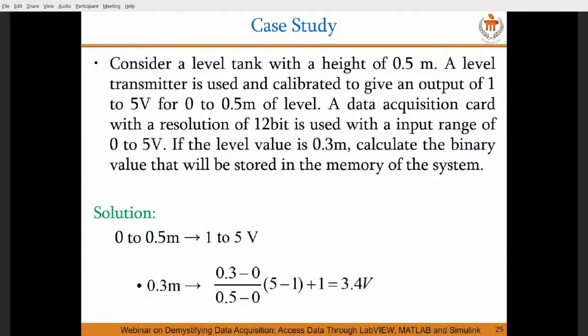0 to 0.5 meters is represented by my sensor as 1 to 5 volt. Now I want to find out what the sensor output is at 0.3 meter. Use the same formula: 0.3 minus 0, upon 0.5 minus 0 as the range, multiplied by 5 minus 1, plus the base value of 1. So at 0.3 meters, the sensor will be giving me 3.4 volt.